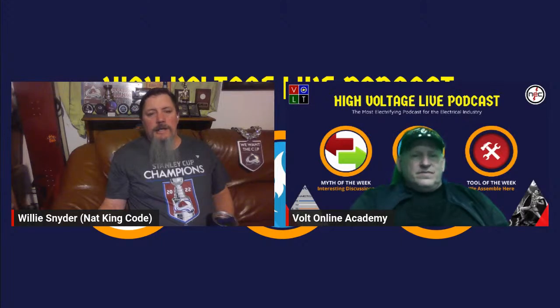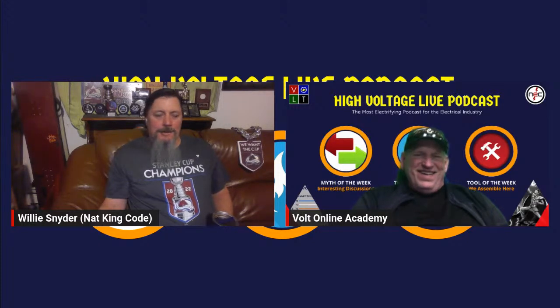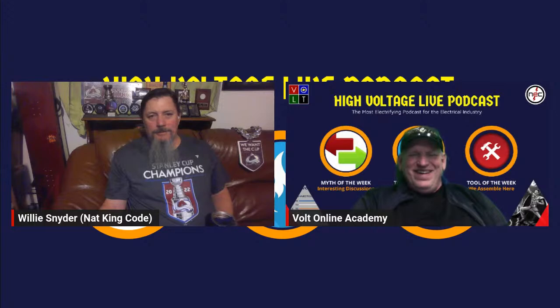Okay. Right. So isn't 110.16 the arc flash label? Mm-hmm. Yeah. So that's kind of one of my favorites. I had a joke about Tommy Davis, where he was saying that you have to put a zip tie or some kind of lock tool, so only a tool can remove the lock on the disconnect. And I said, really, all you need is 110.16. You put a label on there to tell the children that they're not qualified, so they don't open it because they know they're not qualified. So, yeah, the code's already got it in place. So kids are going to read that arc flash label and just know that they're not a qualified person to be opening that cover.